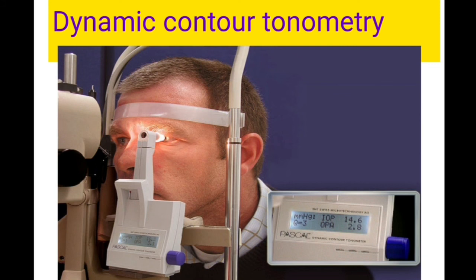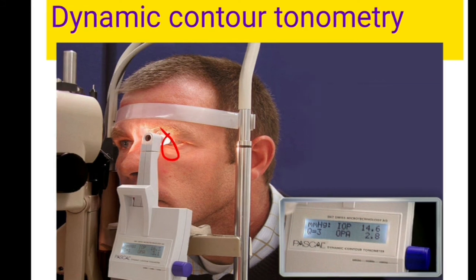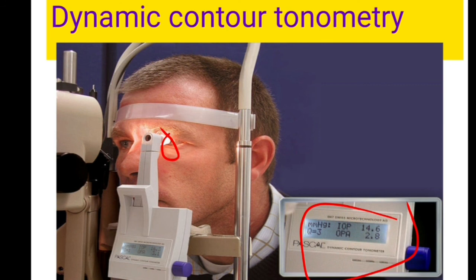Dynamic contour tonometry (Pascal tonometry) has a different principle compared to applanation and indentation tonometry. The principle is: by surrounding and matching the contour of a sphere, the pressure on the outside equals the pressure on the inside. The tip of the probe matches the contour of the cornea, and the pressure transducer built into the center of the probe measures the outside pressure, which equals the intraocular pressure inside the eyeball. The IOP is displayed on an LCD. This is a promising new technology that may give better information about actual IOP and is independent of corneal thickness and contour — the main advantage. It may give readings as accurate as Goldman's tonometry.